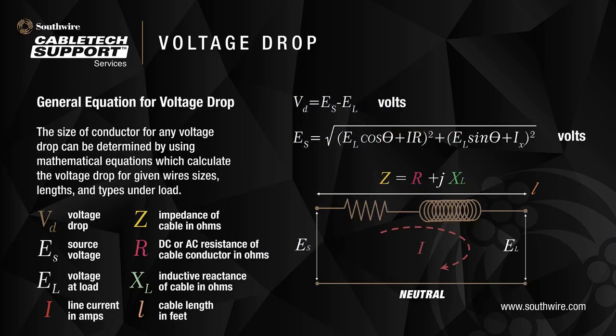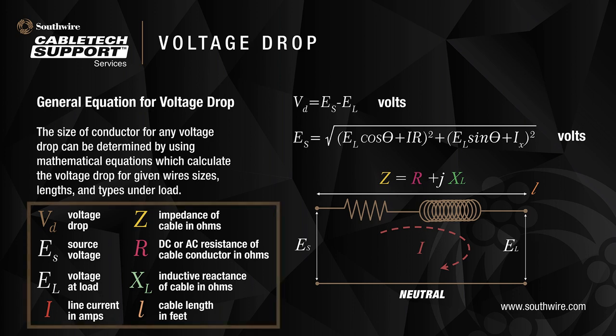The general equation for voltage drop can be used to determine the size of conductor, knowing wire sizes, lengths, and types under load. The main variables involved in the calculations are source voltage, voltage at load, the current in the cable or circuit, the impedance or resistance, and the cable length.